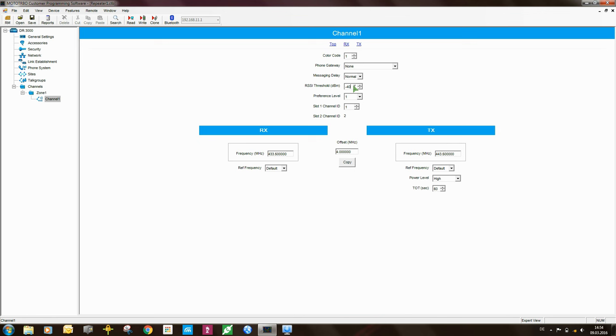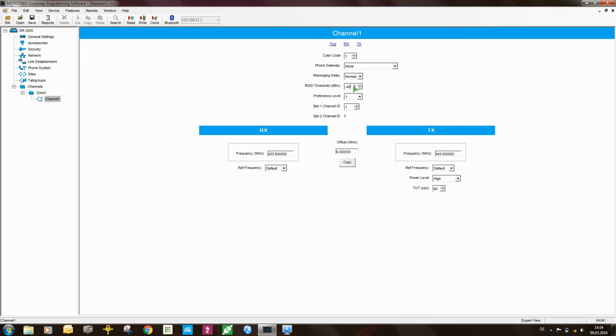When you install the repeater on the site, my recommendation is then to take this RSSI threshold and set it for 10 dB above the noise floor level on the site. So what is the noise floor level on the site? Well, what you have to do is you have to install the repeater, connect antennas and all that, and then you take RDAC and you read the RSSI from the repeater. So basically, when there is no traffic on the channel, you read the RSSI and you should get some value. Usually, if there is no RF noise on the site, somewhere around minus 120 dBm, somewhere there. So, let's say you measure minus 120 dBm, so the RSSI threshold, in that case, you should set it to be minus 110. Or, if you want to be a little bit more safe, minus 100 dBm.